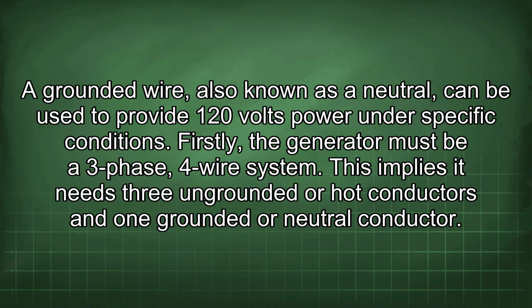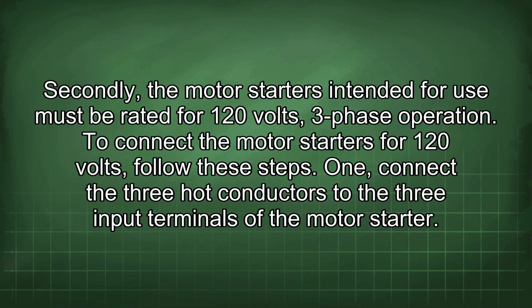The grounded wire, also known as a neutral, can be used to provide 120 volts power under specific conditions. Firstly, the generator must be a 3-phase 4-wire system. This implies it needs 3 ungrounded or hot conductors and 1 grounded or neutral conductor. Secondly, the motor starters intended for use must be rated for 120 volts 3-phase operation.